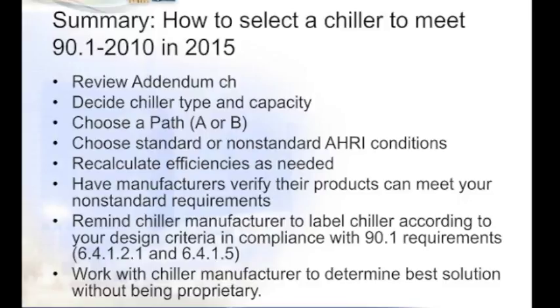And you need to talk to chiller manufacturers. Can their product meet your project needs? Can they test and label it correctly, which is one of their requirements? Is there only one manufacturer that can meet the project requirements, and is that acceptable to your owner or to you? So one of the best things is to read and refer to the specific paragraphs in the standard that apply to your project so that the requirements can be developed, written, and documented, which is also part of what the Energy Code and this particular section requires.